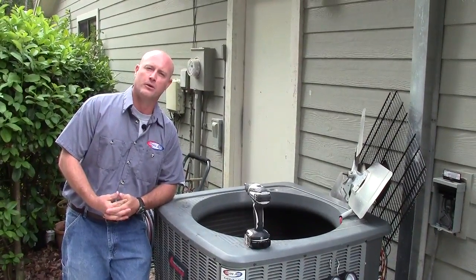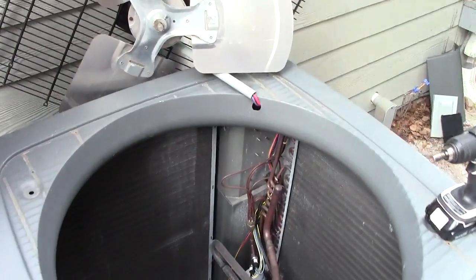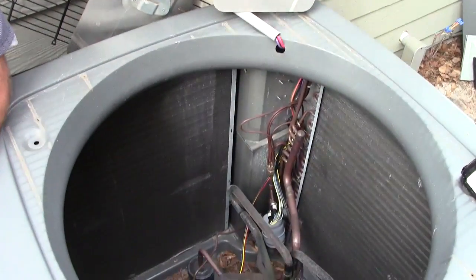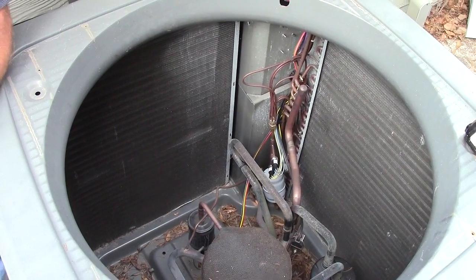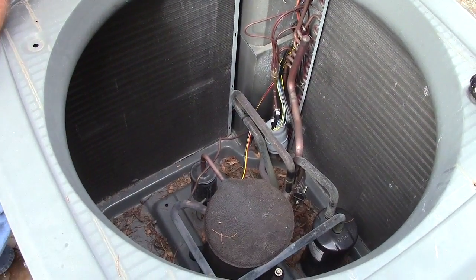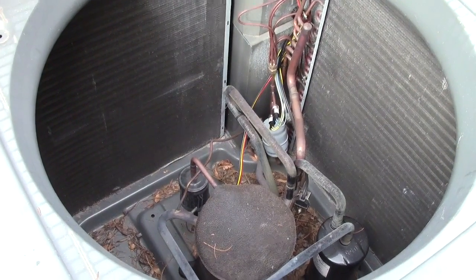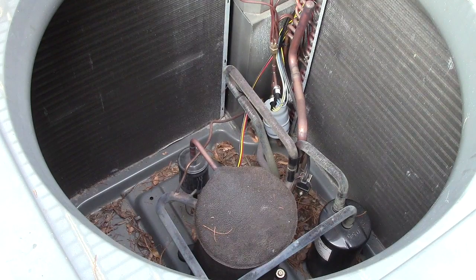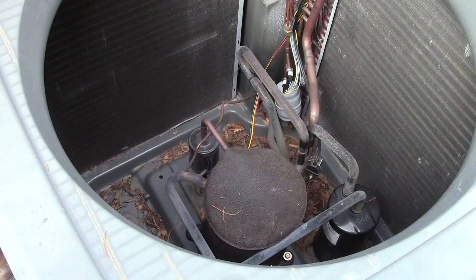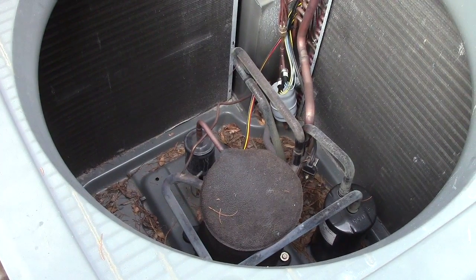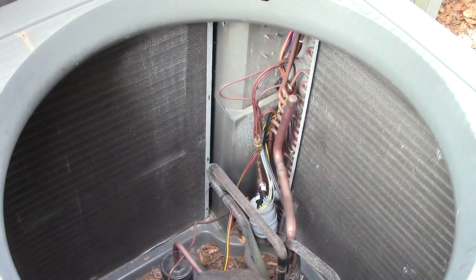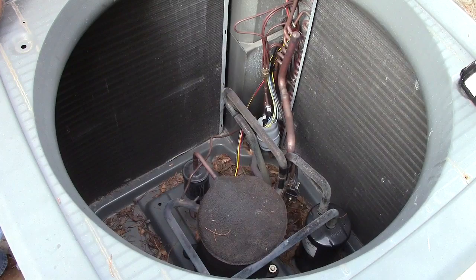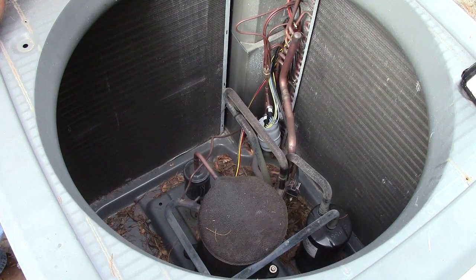Here we're working on an Amana I have opened up for you so we can see some of the items that we are concerned with when we show up at your house. Down inside here, as you can see, are some of the components you'll see in the typical heat pump. This particular brand was an Amana, and you can see that all the pipes inside are not rubbed together or touching, which is what we like to see. No vibrations, no chafing. You'll also see down in here that there's a lot of leaves and debris. It's very important that we get these debris out of here, especially grass clippings. Here in Florida, we see a lot of grass clippings. They will rot the bottom of your machine and destroy your coil if you do not keep it clean. That's why it's so important to have a technician come out twice a year to make sure all this is taken care of for you.